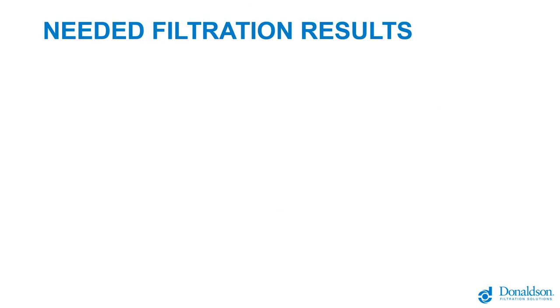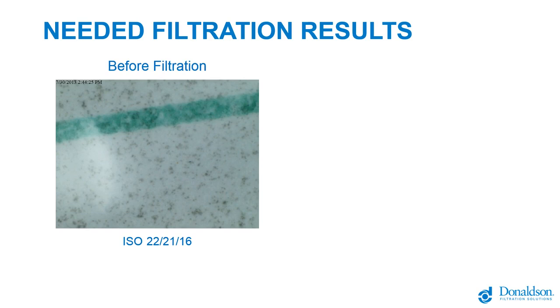So the needed filtration results, just to go over what things typically look like and what you need to achieve. This is a fuel sample out of a small 500-gallon tank that was sitting out in a parking lot for a couple of years, with parking lot dust blowing around, getting into that tank with very little fuel usage out of it. It wound up with a ton of fine particulate in here.